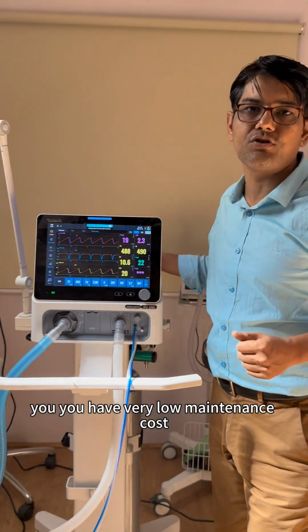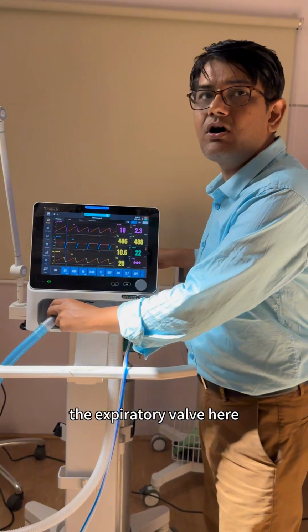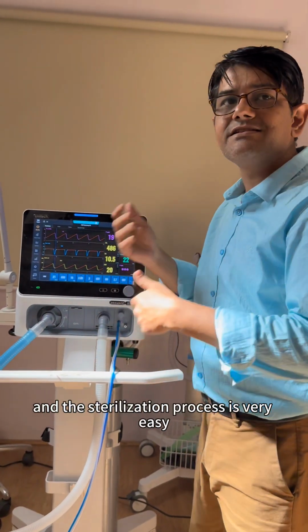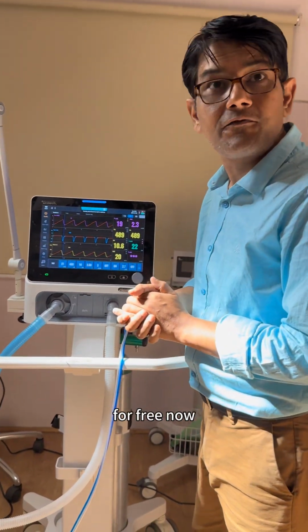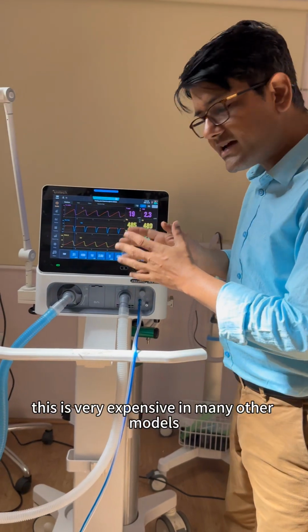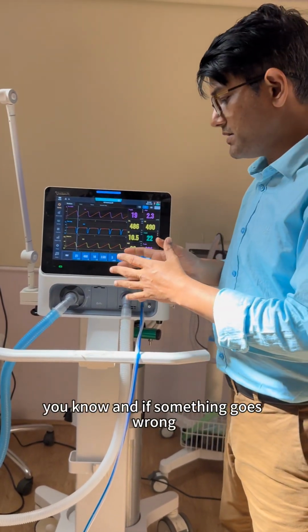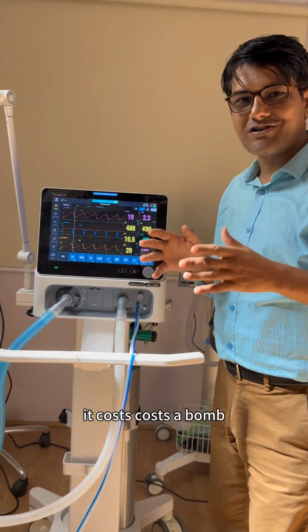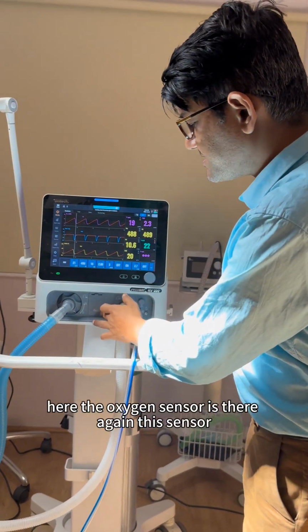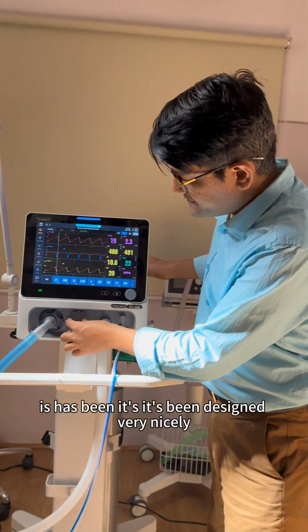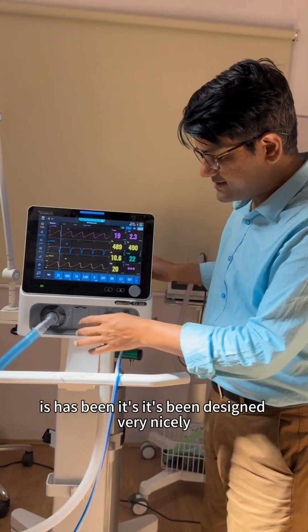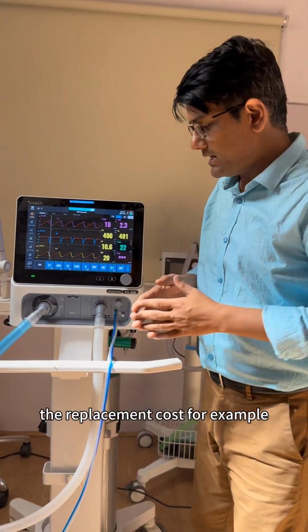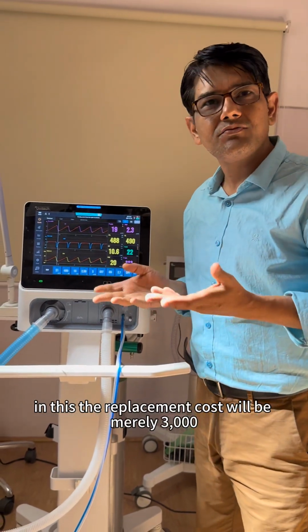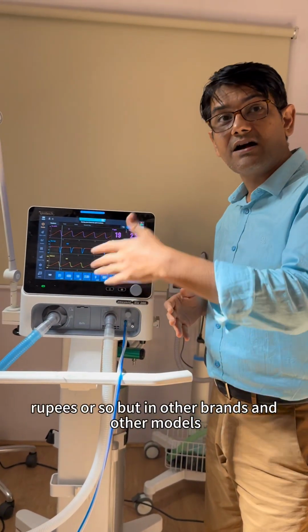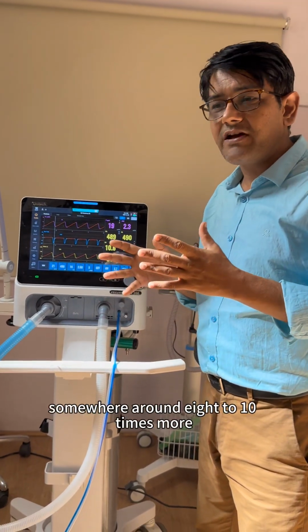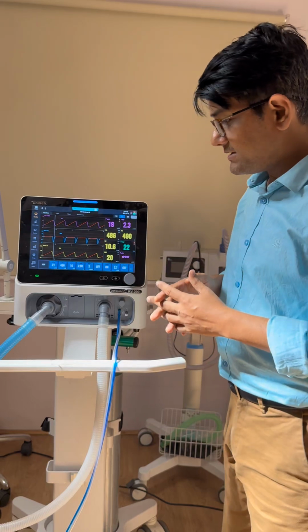You have very low maintenance costs. This is one very important point. The expiratory valve here is very easy to take out, and it can be sterilized for free. This is very expensive in many other models, and if something goes wrong, it costs a bomb to you. Here the oxygen sensor is designed very nicely. The replacement cost in this is merely 3,000 rupees or so, but in other brands and models, the oxygen sensor costs somewhere around 8 to 10 times more. So that's one big saving you're getting.